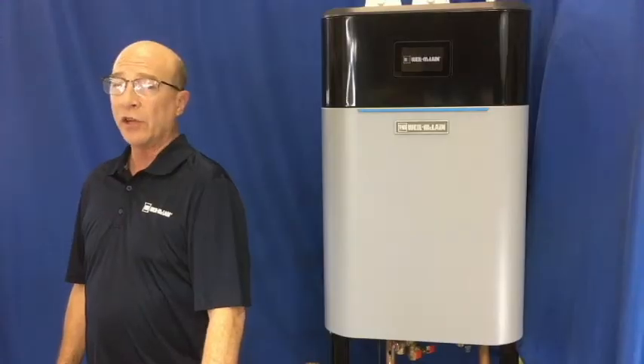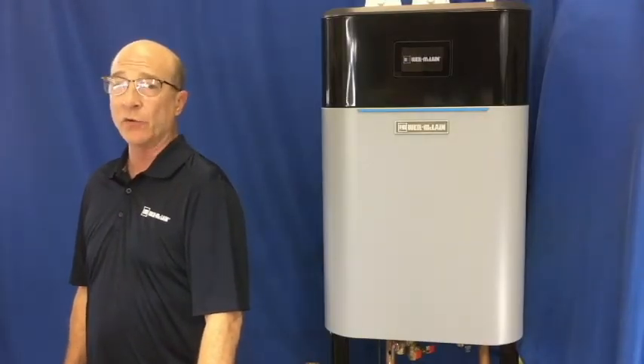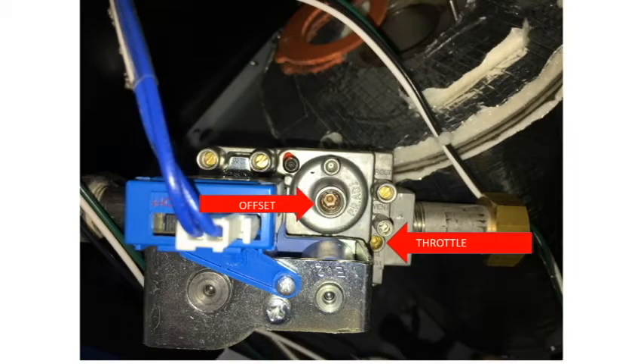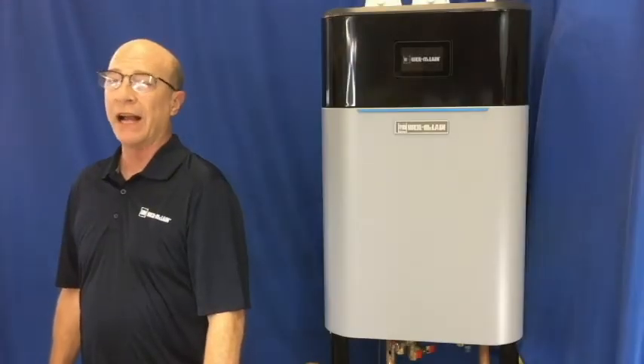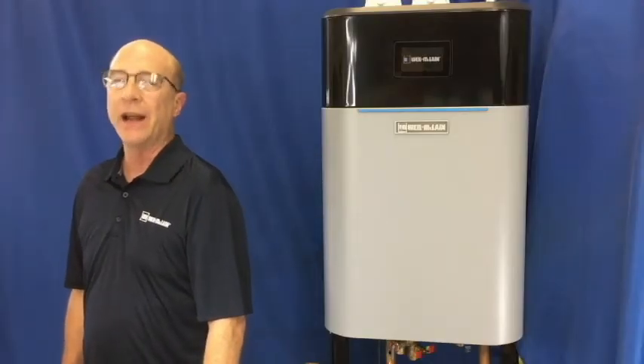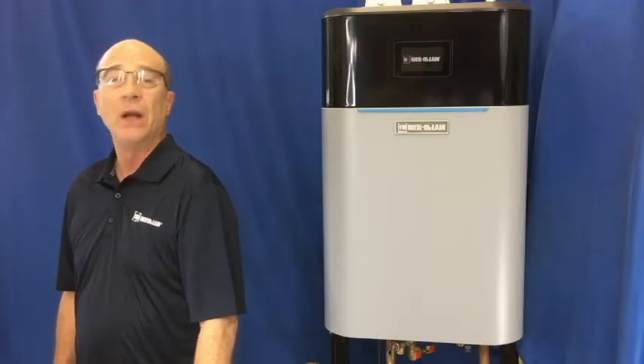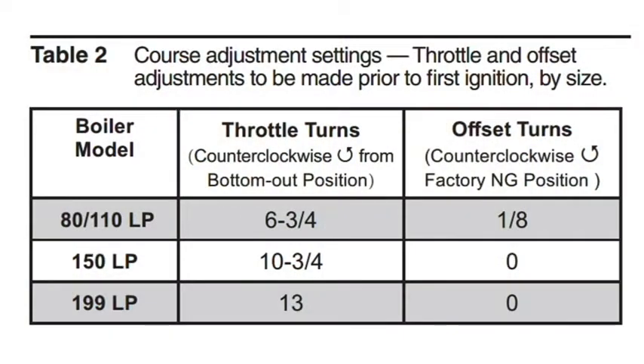Next, we want to locate the throttle screw and the offset screw on the gas valve. Keep in mind, we adjust the throttle in high fire and the offset in low fire. If the unit is running on natural gas, no adjustment is needed on the throttle or offset screw to begin testing. For LP gas, make the needed adjustments if this is the first time firing the boiler. It is very important to make these adjustments before firing the unit on LP gas.